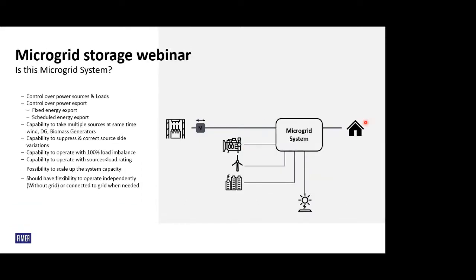Then what exactly is a microgrid? A microgrid works like a black box, which can take multiple sources, not only the grid, and it can also work isolated from the main grid. You can in fact set priorities for which source has to be utilized first and second. Those priorities keep changing country to country, because in India diesel power might be the costliest, whereas in the Middle East they would prefer using diesel generators because the fuel cost is less. With a microgrid system, since it works like a black box, we can have the optimal energy mix as we want, and complete control over each of the power sources.